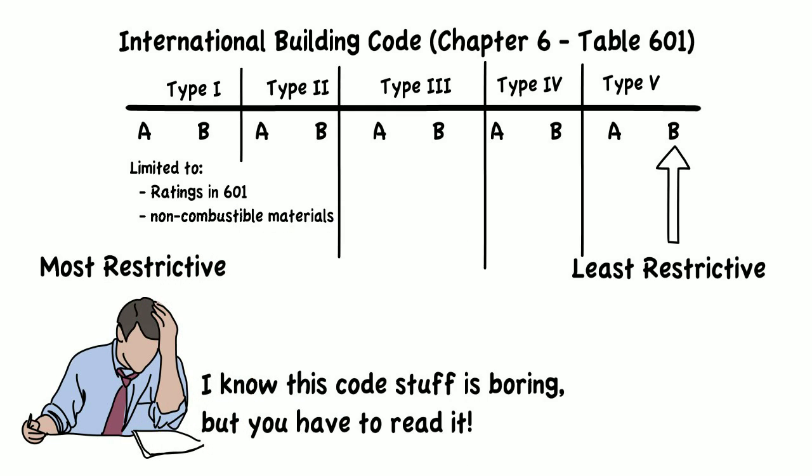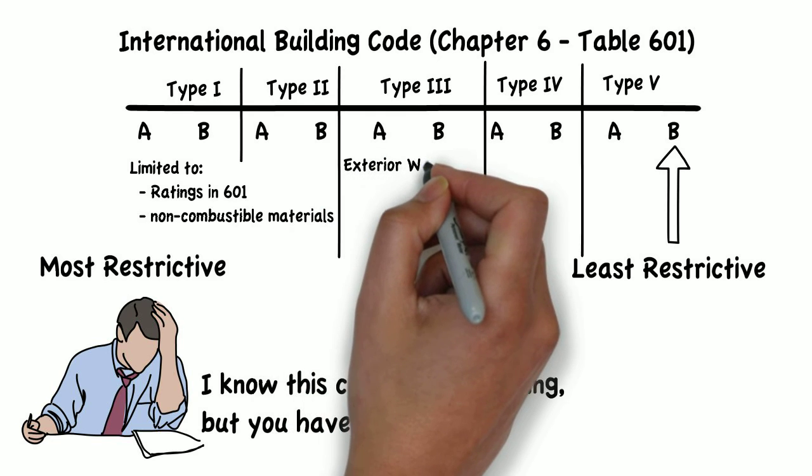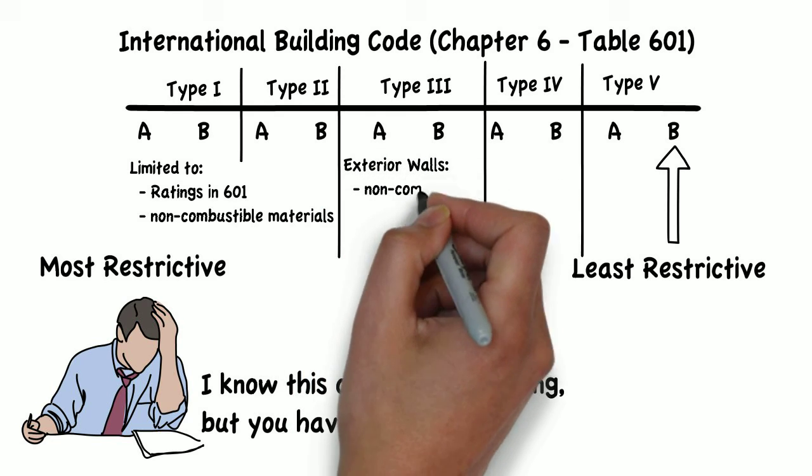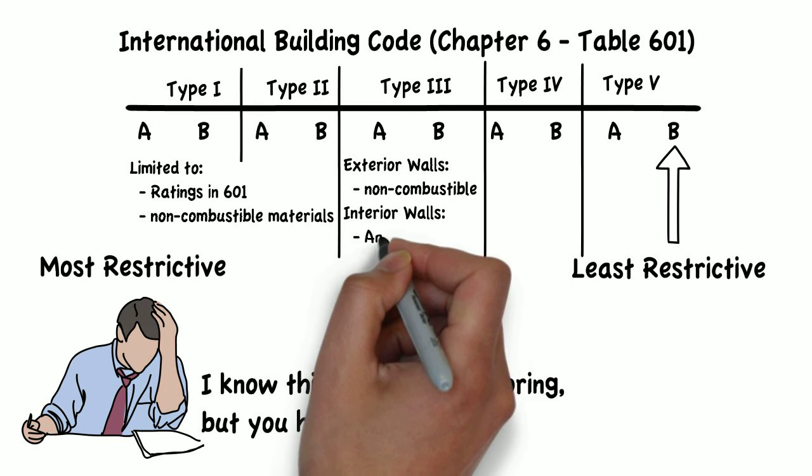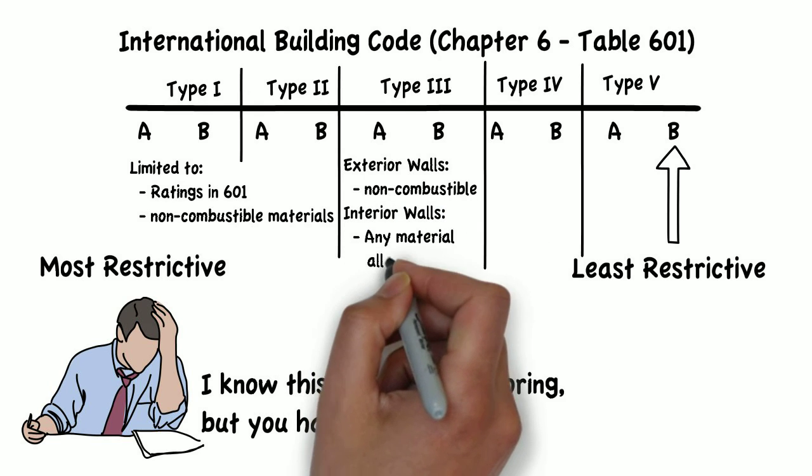IBC Section 602.3 tells us that Type 3 buildings have exterior walls of non-combustible materials and interior elements of any material permitted by the building code.